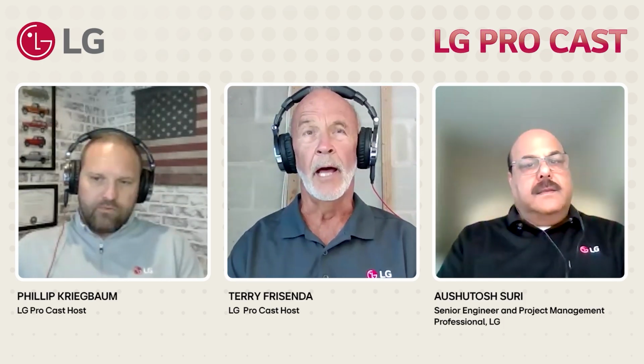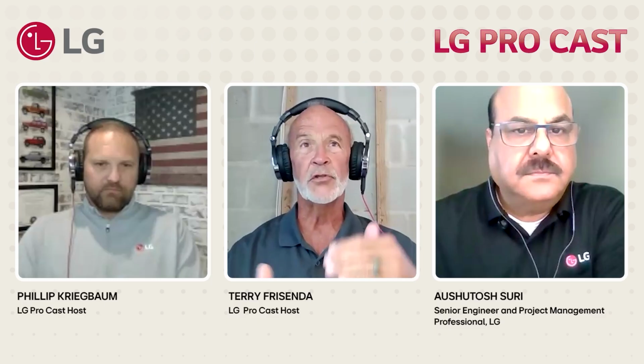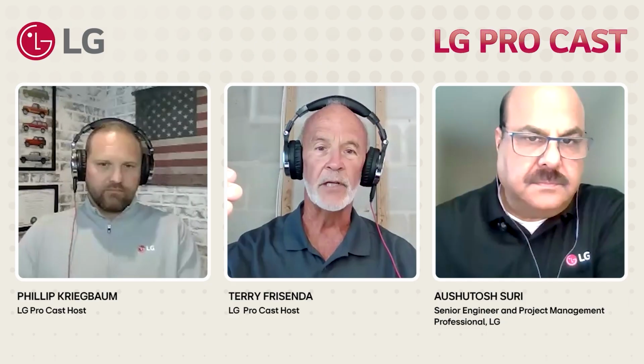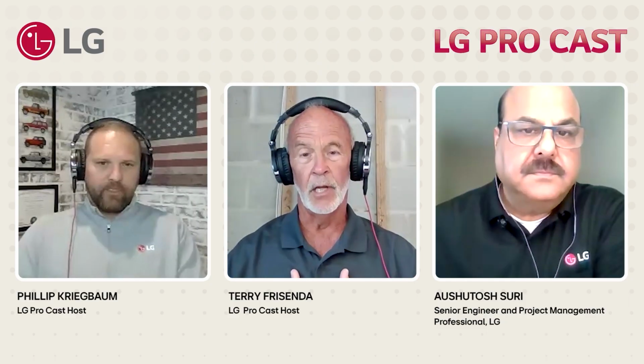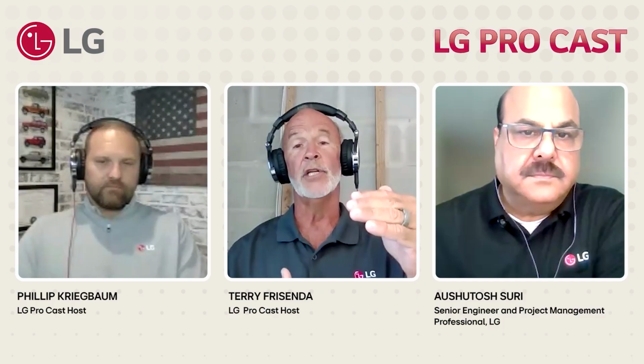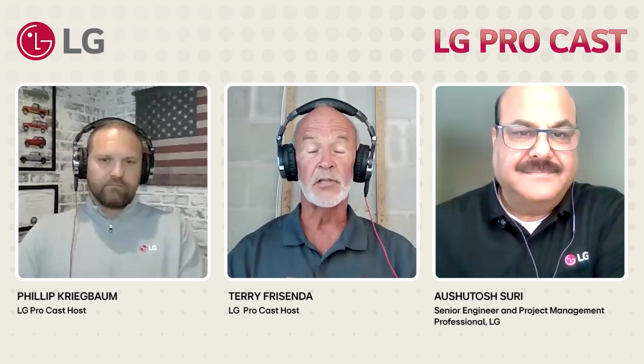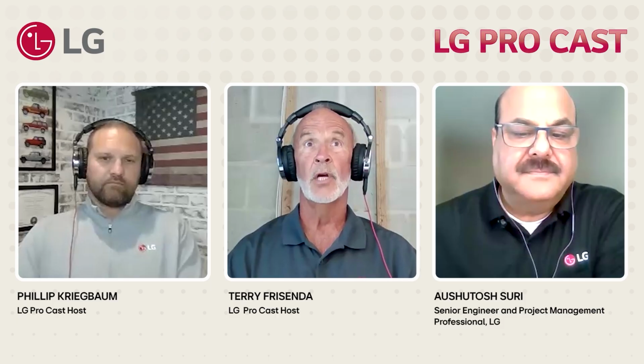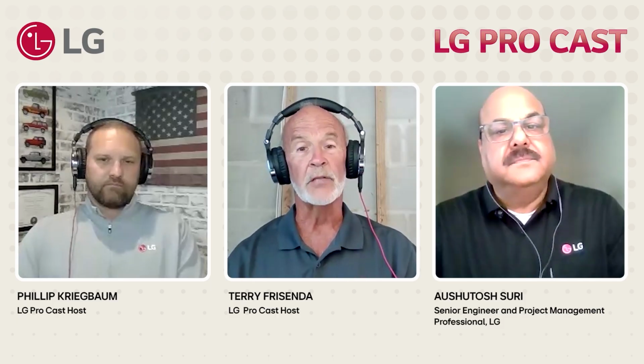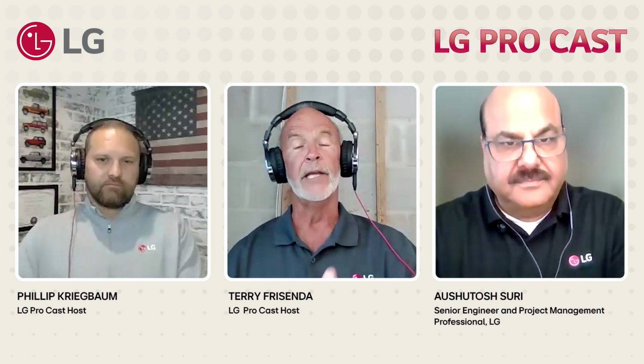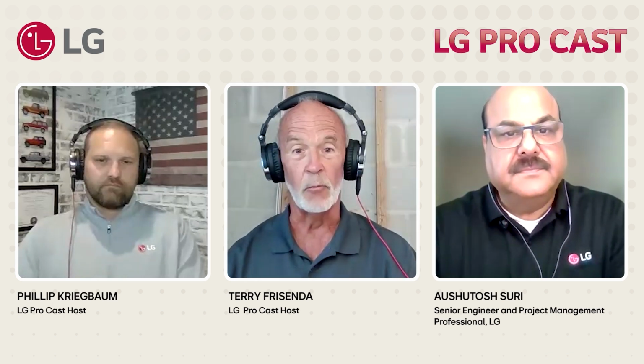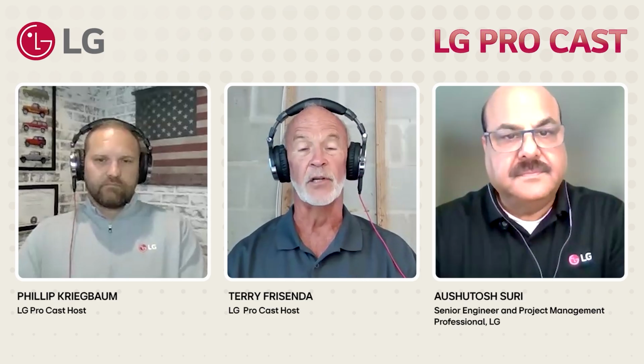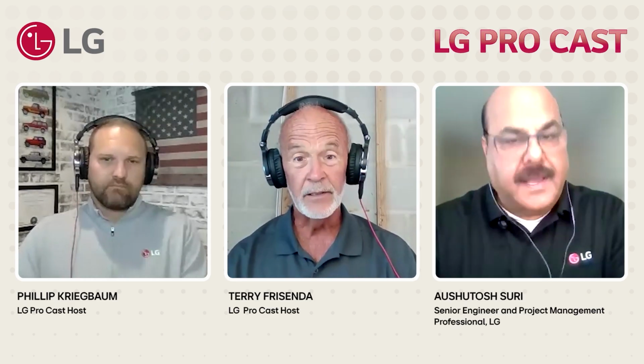Hang tight, rather. I know if I'm thinking it, some of the folks watching this podcast are thinking as well. With this 2 EEV operation, I've got an electronic expansion valve in the indoor unit and one in the outdoor unit, and what that does is allow LG to use an existing line set, right? Now we have a product that allows the contractor to use that existing line set. And if I understand the way the system works, in the cooling mode the outdoor unit expansion valve will be the valve working, and in the heating mode the indoor unit expansion valve will begin. So we are actually using both of those expansion valves in the course of normal operation. Is that correct? Absolutely correct.